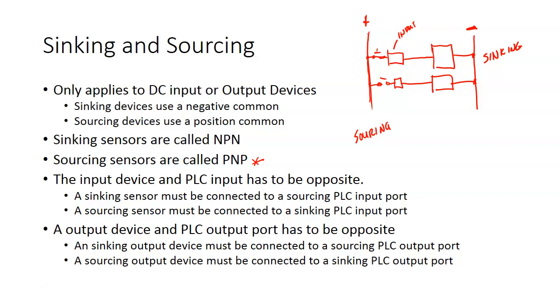Over here in the U.S., it's popular to run sinking inputs, which means you need to buy PNP sensors. And the outputs in the U.S. are usually sourcing outputs, so they output the plus, and you need to connect the minus to your output devices. We don't really worry about that as far as lights go. Light indicators don't care about polarity.